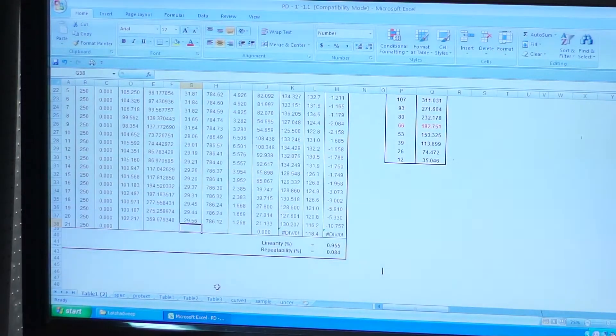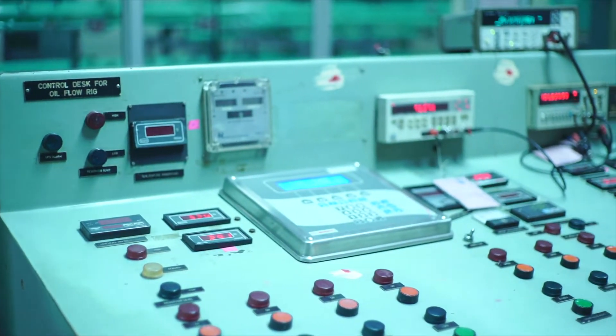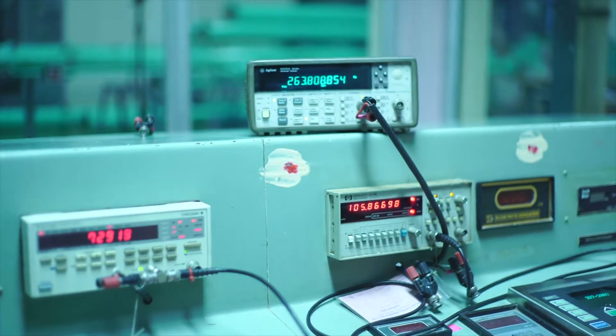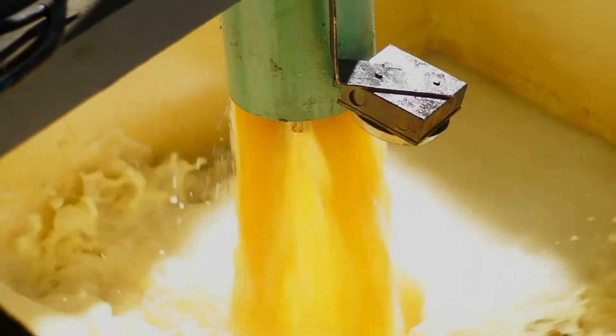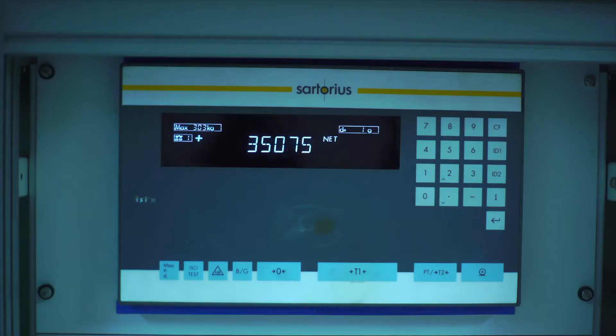The lab also conducts third-party witness testing and auditing of metering stations at site as per API standards. The laboratory has a multi-viscous oil flow facility which can calibrate flow meters in different viscosities ranging from 2 centistokes to 400 centistokes.